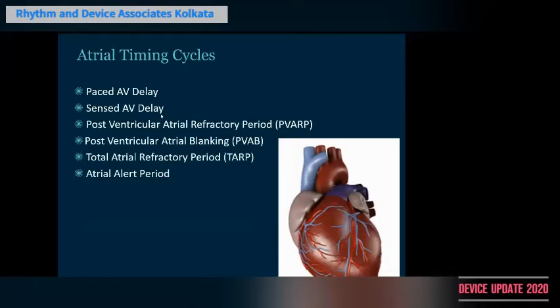So these are the four basic periods that you have to remember. Also remember that there is something called the total atrial refractory period. It is basically the sum of your sensed AV delay along with your post-ventricular atrial refractory period. It's called total atrial refractory period because it means the total period in which any event in the atrial channel will not be picked up and will be marked as refractory. Anything other than that falls in the atrial alert period and also in the ventricular alert period.